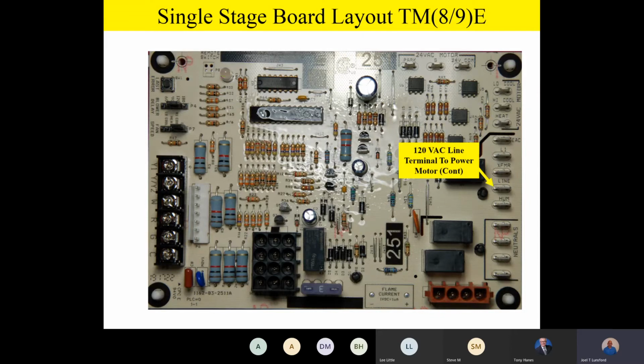Now remember, we said that on an ECM type of motor, we have power to it all the time. Well, that's where we power the motor up all the time, is where it says line. That goes over to the ECM motor. That's the hot power, if you will, or 120 volt line voltage to the ECM motor all the time. Now remember, team, that motor's not running. It's waiting for a 24 volt command to tell it what to do, but we have power to it all the time.